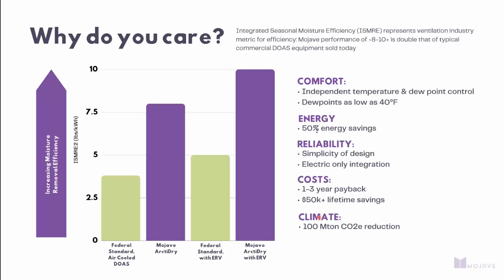So much more precise level of control due to that decoupled approach in terms of hitting set points and meeting application demand. Additionally, with the pairing with liquid desiccant technology, we're able to deliver dew points that were originally only achievable with industrial level equipment. We could achieve dew points as low as 40 degrees, in some cases even lower, down into the 35 degree dew point range.